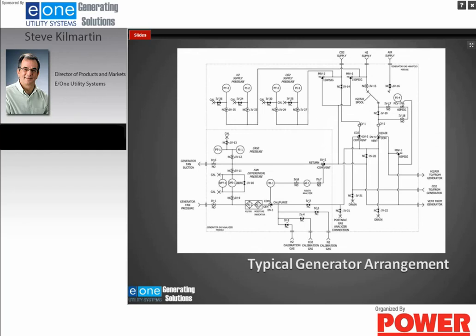Back to the P&ID that I showed you earlier, and again, under normal operating conditions when the generator is running, I'm going to be taking my sample from the generator fan pressure and the generator fan suction. During the purging process, I'm going to take the three-way valve on the bottom of the flow meter, change it so that it's taking the sample from the right-hand side, and I'm going to have the isolation valve that's in line with the purge open, and that goes to the vent from the generator as we discussed in the previous slide. So now my sample is going to come from the vent line of the generator.